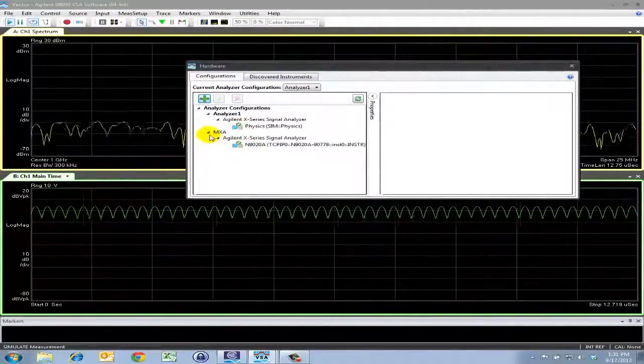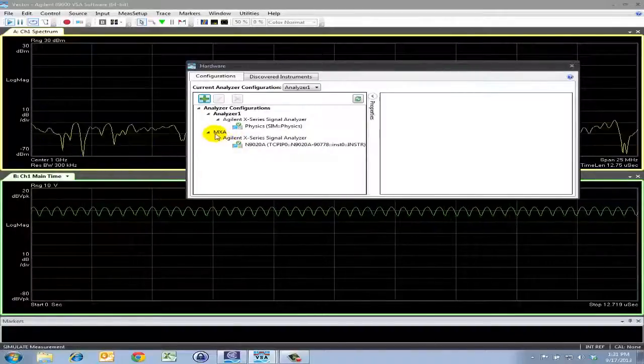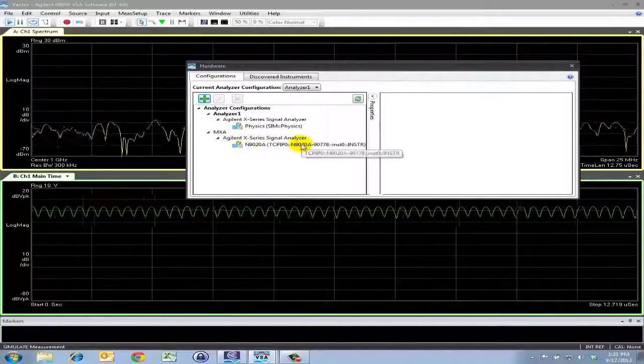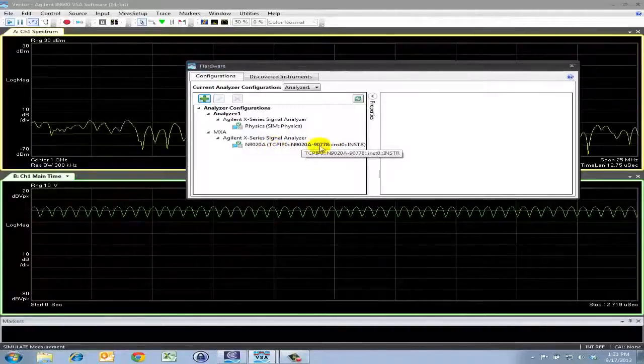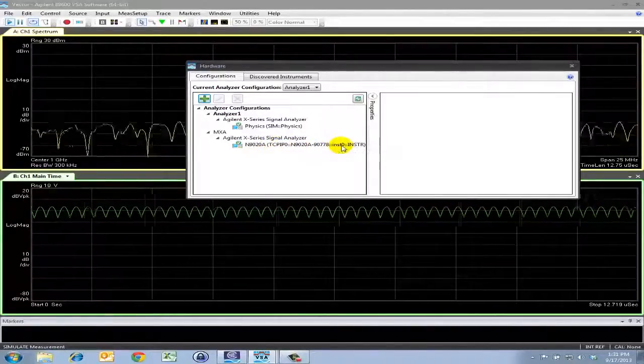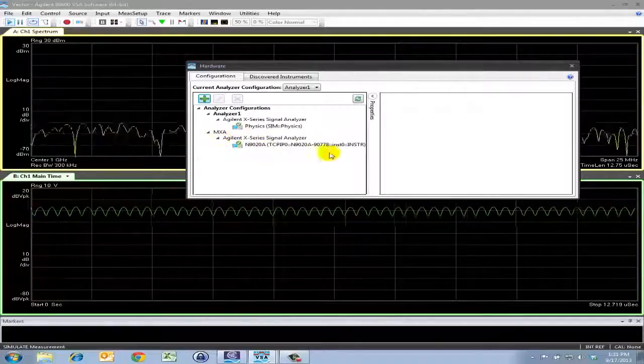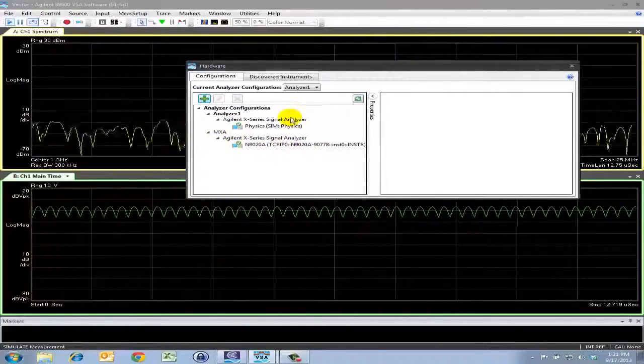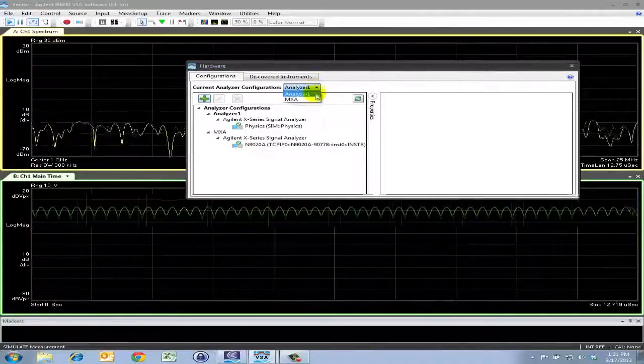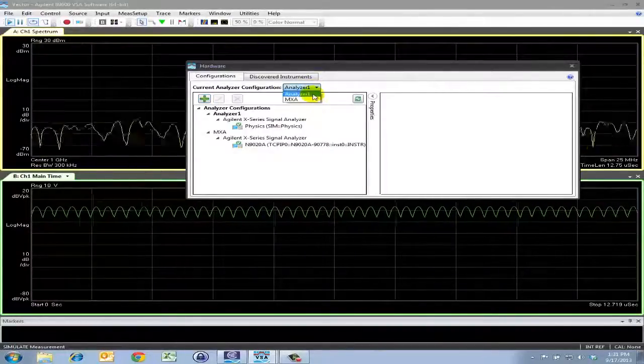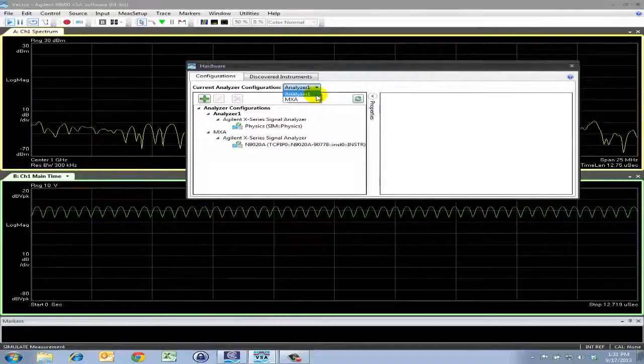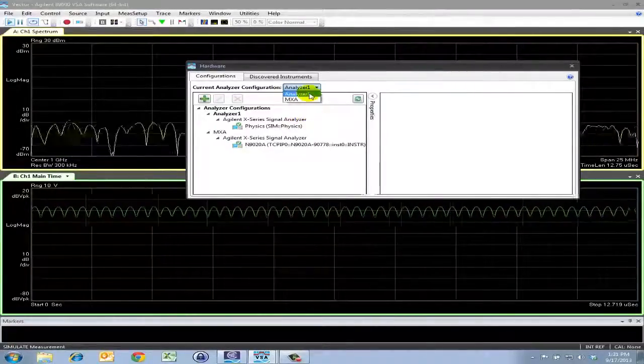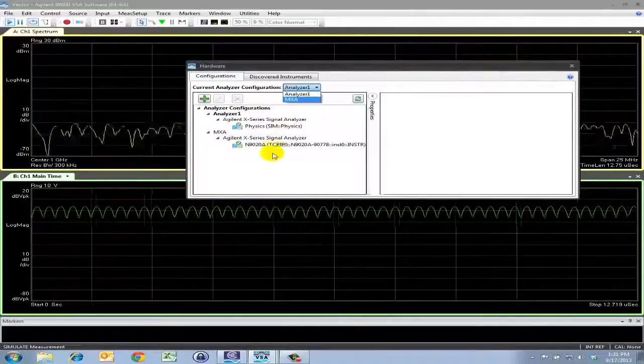Now you'll see that a new analyzer configuration has appeared. MXA here is what we had just called it, and I can confirm that this is the same address that I have set in the Agilent Connection Expert. Now we still have not yet made a connection to the analyzer. If you notice, there is another drop-down menu here, which shows a list of all the different configurations that we've set up. So analyzer 1 is the default analyzer for simulation mode, and the MXA is the one that I just set up.